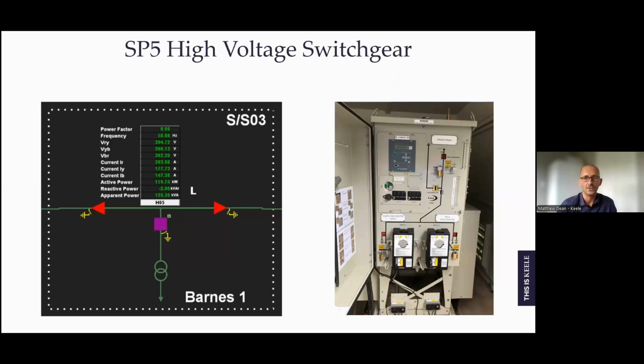So as part of the SEND project, we retrofit remote actuators onto the front of the switchgear. So that's an example of some switchgear there in the substation. We retrofit remote actuators onto the front and also added fault passage indicators. So what those pieces of hardware enable us to do is something called FLISR, which stands for Fault Location, Isolation and Service Restoration.